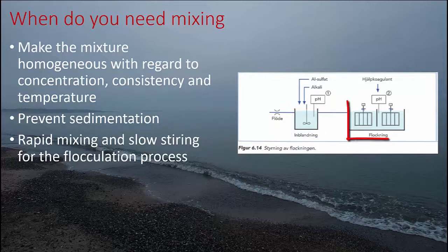Second tank, you have the flocculation tank or flocculation chamber. In this you have slow mixing in order to get the small flocks in contact with some other small flocks to make bigger flocks, so they fall faster. Here the mixer will do that, but also it's importantly the speed cannot be too high, because then you start destroying the flocks that are formed.